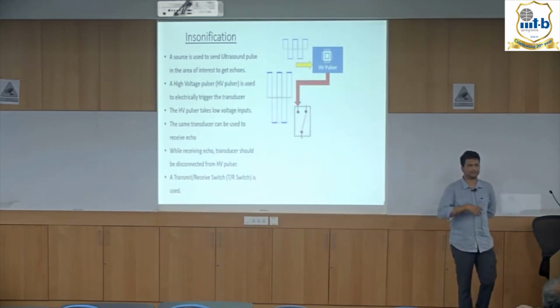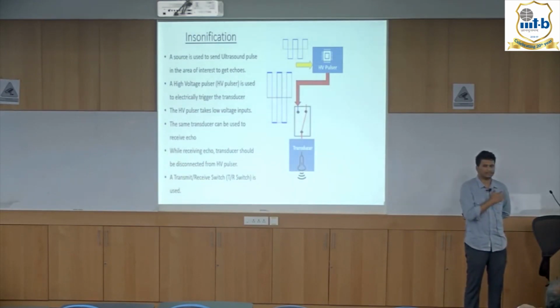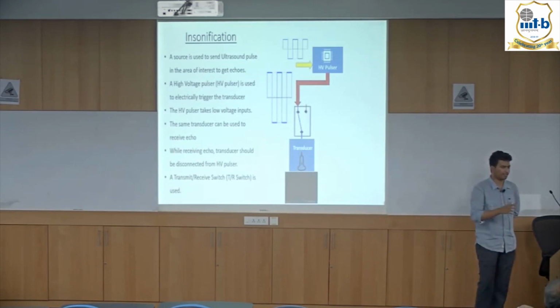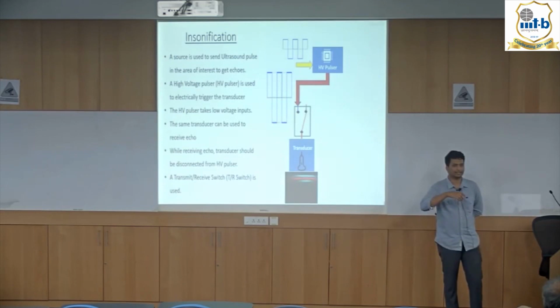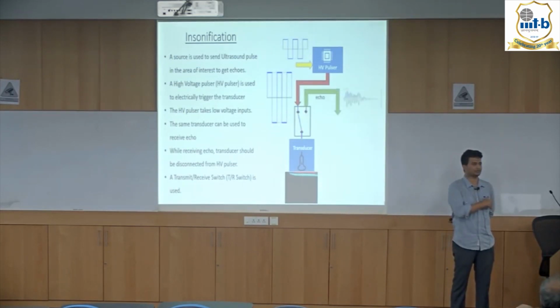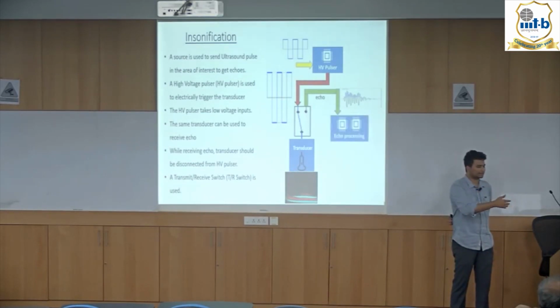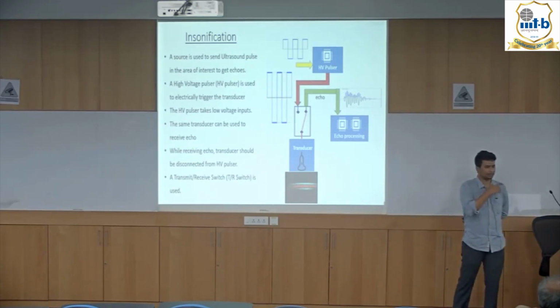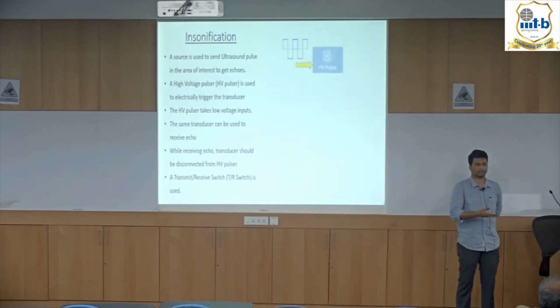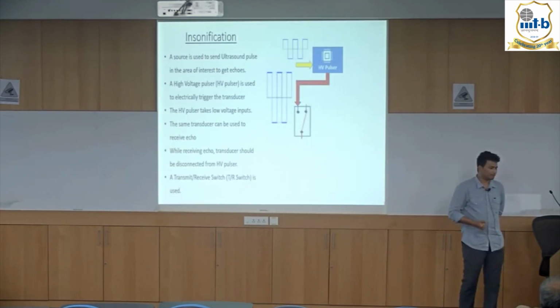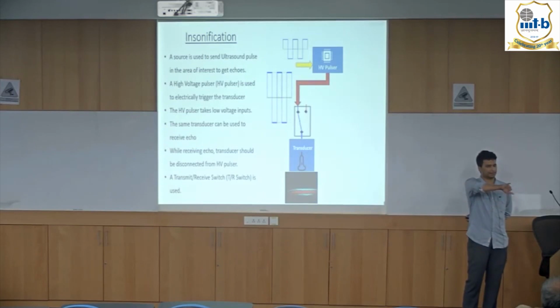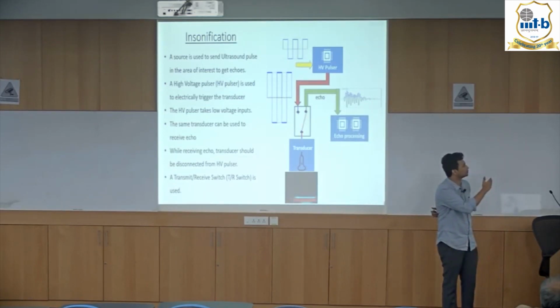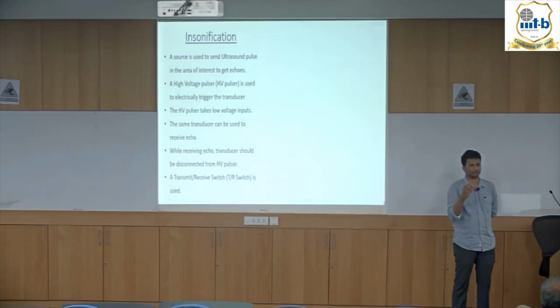To transmit an ultrasound wave, there's a circuit called a high voltage pulser, which generates a high voltage electric pulse that can be applied to the transducer. The input to this circuit is a low voltage signal, as you can see there. It is typically controlled by a processor or controlling unit within another part of the system. Once the ultrasound is transmitted, the received echo is diverted to another part of the system where it gets processed. So there is a switch which switches the transducer from the high voltage circuit part to the echo processing part. It's called a TR switch.